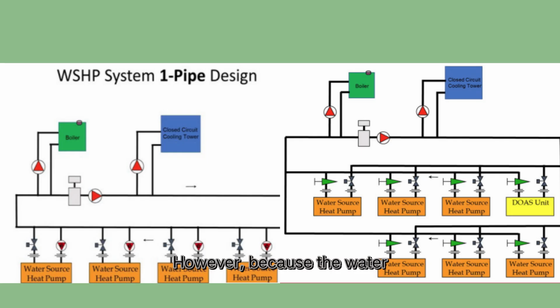However, because the water flows in a single direction, each unit experiences slightly different entering water temperatures depending on its position in the loop. Second, the two-pipe WSHP system. Here, the system uses separate supply and return lines, so all heat pumps receive water at the same temperature. This design typically includes automatic shutoff valves to improve efficiency and protect compressors when units are off.